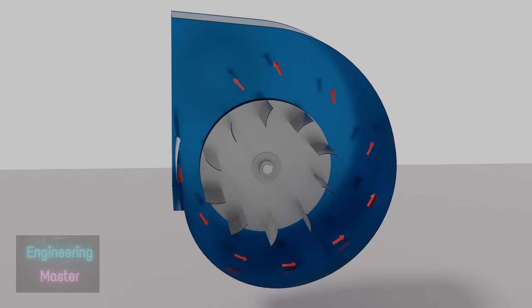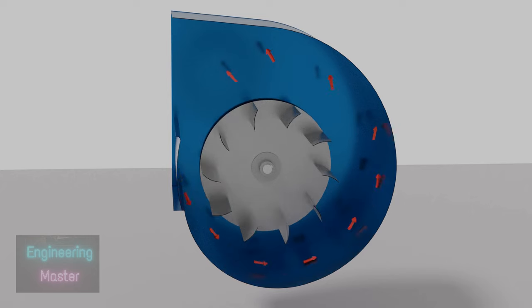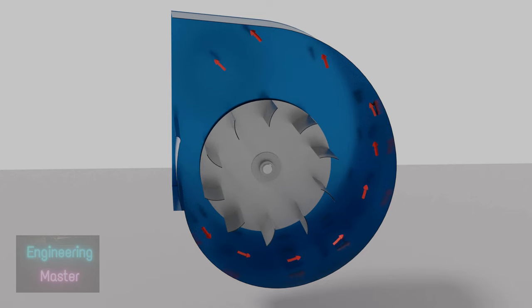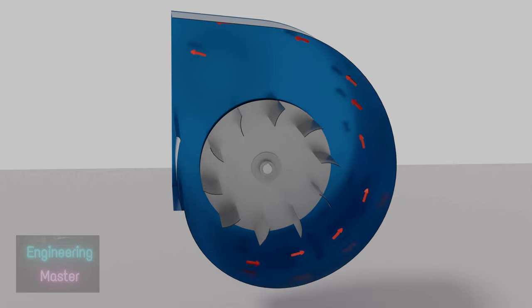Then air moves in a spiral direction. Both the effects will increase its static pressure and velocity pressure. When the air reaches to the casing, air gets slowed down a little, which increases the static pressure at the expense of the reduced velocity pressure.